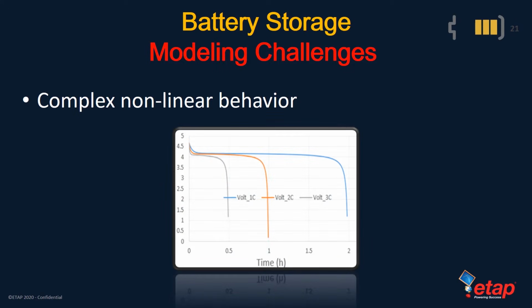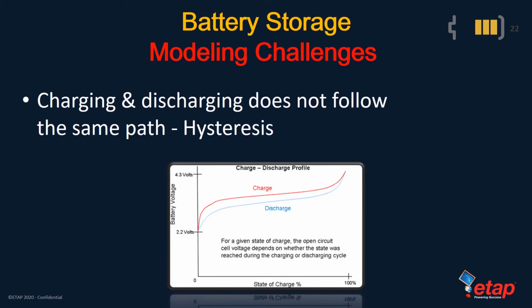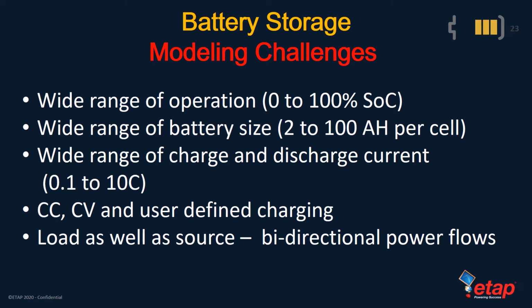Before we get to the program, let's take a look at some of the modeling challenges and the need for some of these capabilities. So one of the modeling challenges for battery energy storage is the complex nonlinear behavior of the charge and discharge curves. And as we have seen earlier, the various C rates that may be possible and provided by the battery manufacturer follow different charge and discharge profiles. And as we can see, the charging and the discharging curves do not follow the same path. There is a hysteresis that is typically applicable that depends upon the chemistry of the battery, allowing or preventing the charging and discharging to not follow the exact same path. Other modeling challenges include the wide range of operation, so you can vary the battery from 0 to 100% state of charge and get different results.